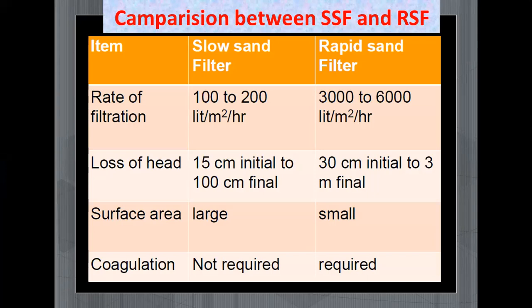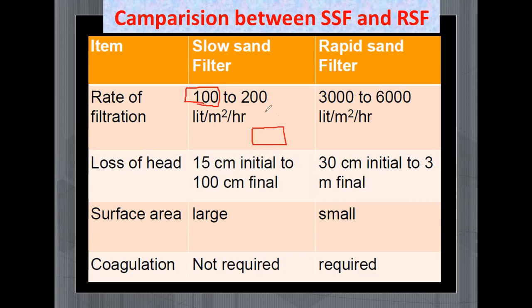The first point of comparison is the rate of filtration. In the slow sand filter the rate of filtration is 100 to 200 liters per meter square per hour. That means if we consider one meter square area of a filter media, through that area within one hour we can filter only 100 liters of water. But in the rapid sand filter the rate of filtration is very high — it is 3000 to 6000 liters per meter square per hour.